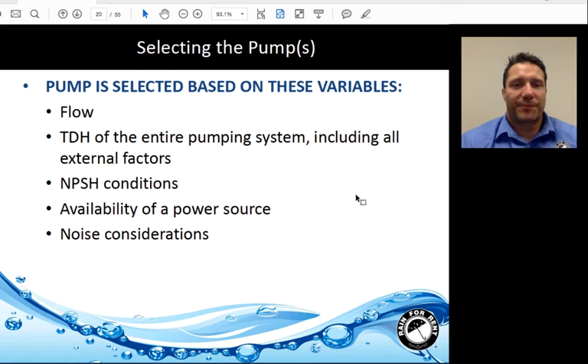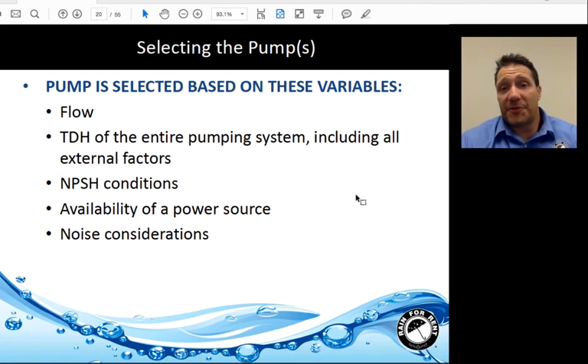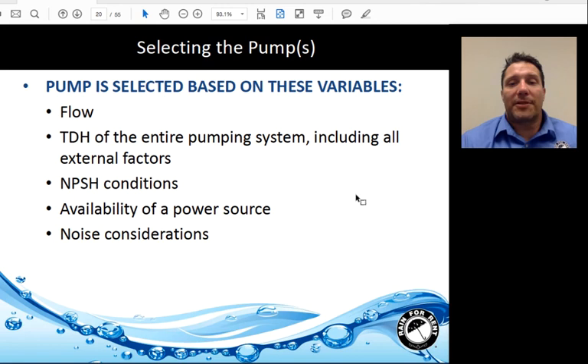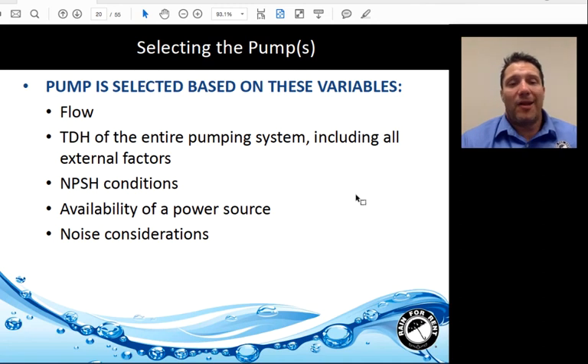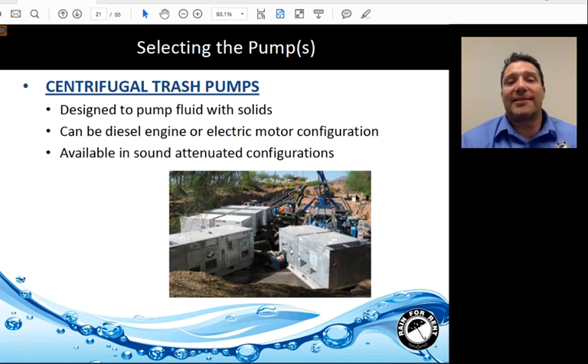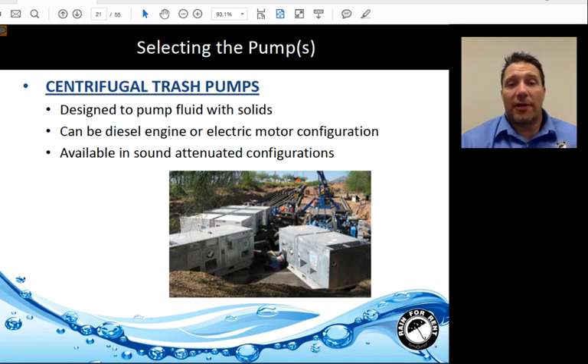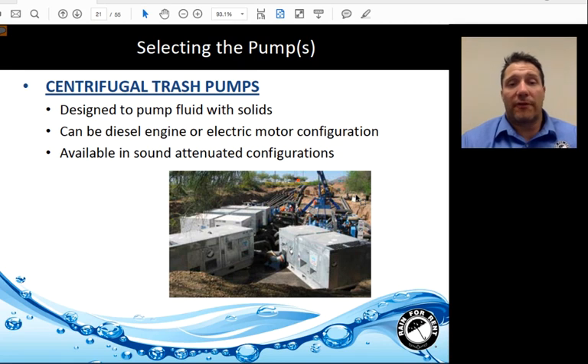Bypass system design: Pump selection is based on flow, TDH of the entire pumping system including all external factors, net positive suction head conditions, availability and type of power source, and noise considerations. A centrifugal trash pump is designed to pump fluids with solids in it. It can be in diesel engine or electric motor configurations, and is also available in sound-attenuating configurations.